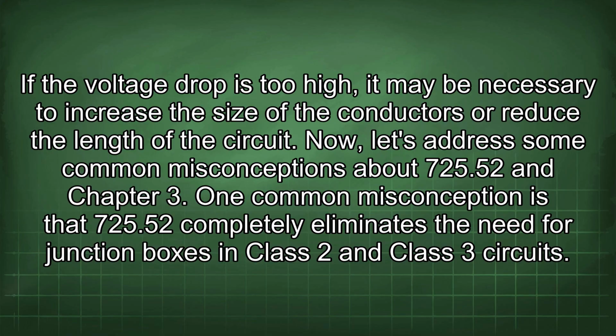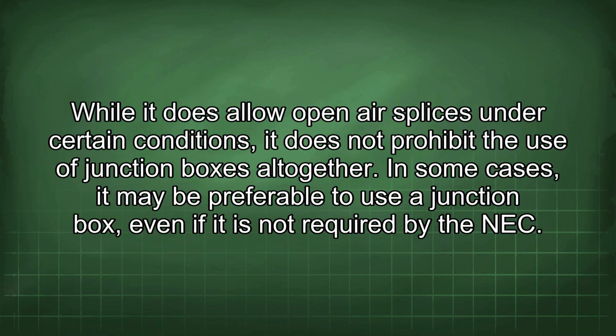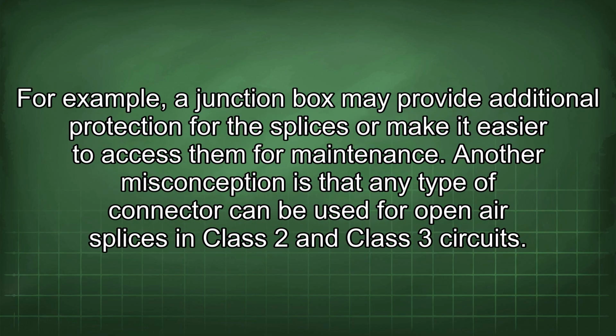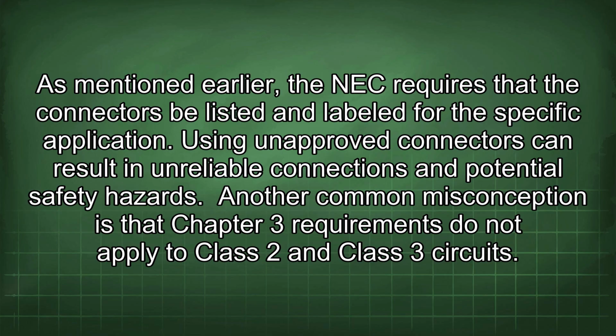Now, let's address some common misconceptions about 725.52 and Chapter 3. One common misconception is that 725.52 completely eliminates the need for junction boxes in Class 2 and Class 3 circuits. While it does allow open-air splices under certain conditions, it does not prohibit the use of junction boxes altogether. In some cases, it may be preferable to use a junction box, even if it is not required by the NEC. For example, a junction box may provide additional protection for the splices or make it easier to access them for maintenance. Another misconception is that any type of connector can be used for open-air splices in Class 2 and Class 3 circuits. As mentioned earlier, the NEC requires that the connectors be listed and labeled for the specific application. Using unapproved connectors can result in unreliable connections and potential safety hazards.